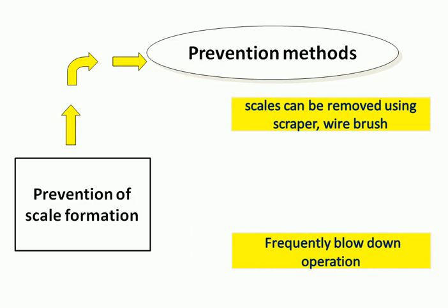What is the prevention of scale? What methods are followed for scale prevention? Scales can be removed by using a scraper and wire brush — the rubbing method. Another method is thermal shock, used to remove the layer of scales from the metallic surfaces. Another method is the frequent blow down operation. In the blow down operation, during maintenance, the steam production is stopped for heating, all the salt deposits settle at the bottom of the boiler, the valve is opened, and the loosely precipitated salt deposits come out. Doing this frequently reduces scale formation.